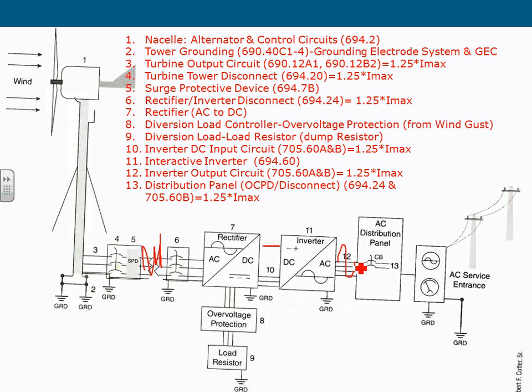If you dump the power into the grid, they require you to have a UL listed interactive inverter, like they do in the solar system. When you have interactive for a solar system, it's the same way. You have to have a UL listed inverter. They call it anti-islanding. So you have the same requirement, anti-islanding.